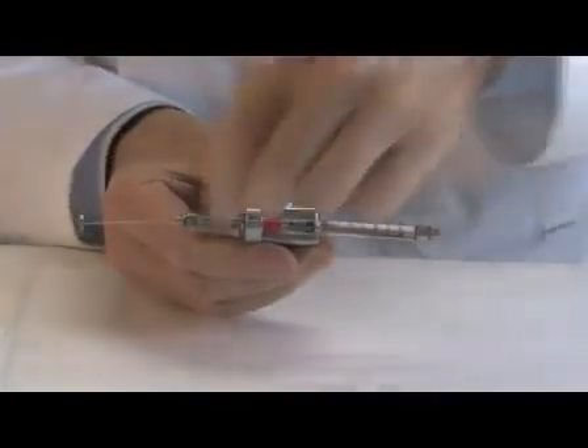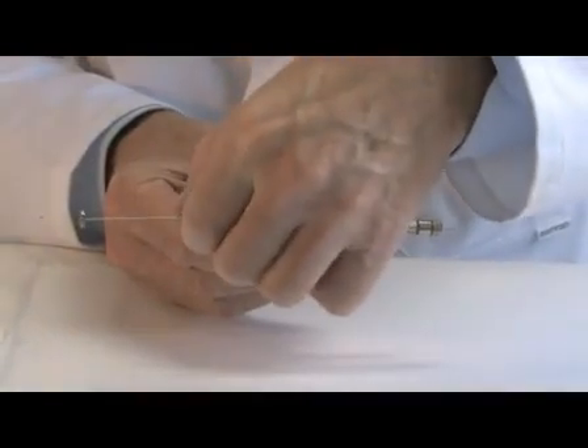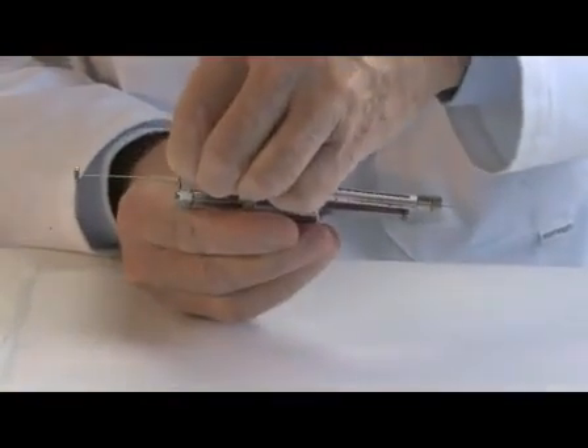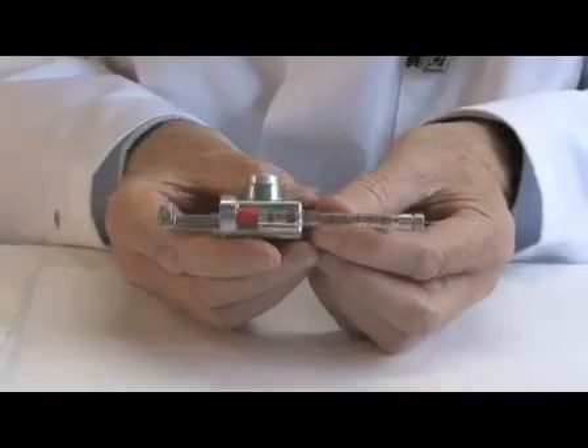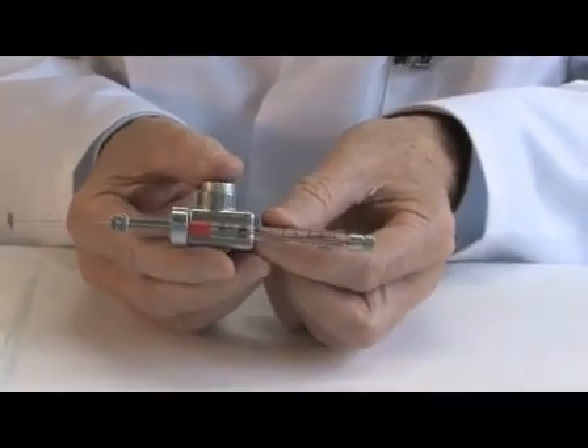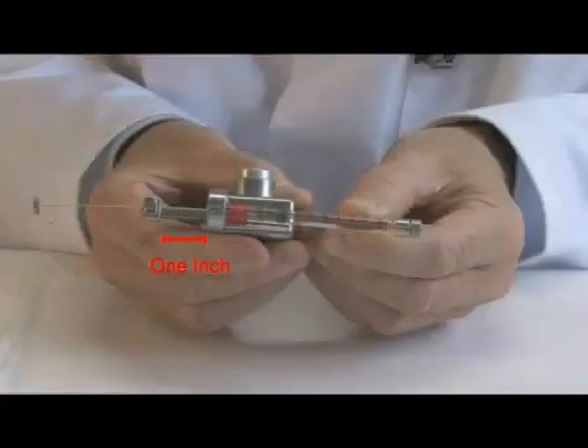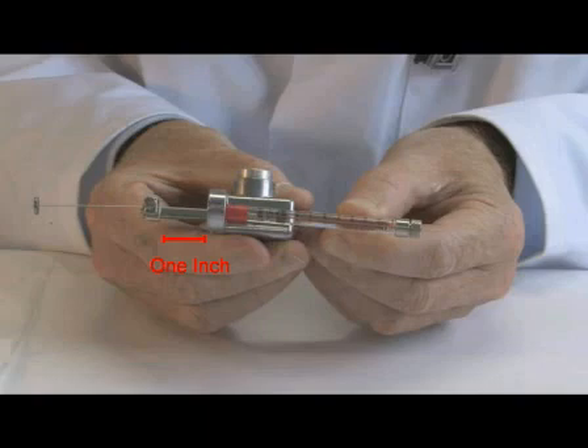Clamp the plunger to the ratchet arm by tightening the nut in the gripping ring. Care should be taken not to over-tighten the nut, as this can score and deform the plunger, rendering it unusable. It is important that the travel range provided to the ratchet arm in the clamped condition be limited to no more than 1 inch as shown. Beyond this, the plunger will have a tendency to buckle and delivery can fail.